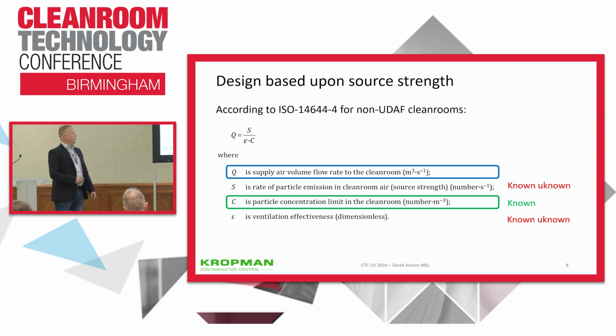And we have one known value. The known value is the maximum particle concentration in your clean room according to the ISO class. But we have two known unknowns. That is the source strength and that is the ventilation effectiveness.